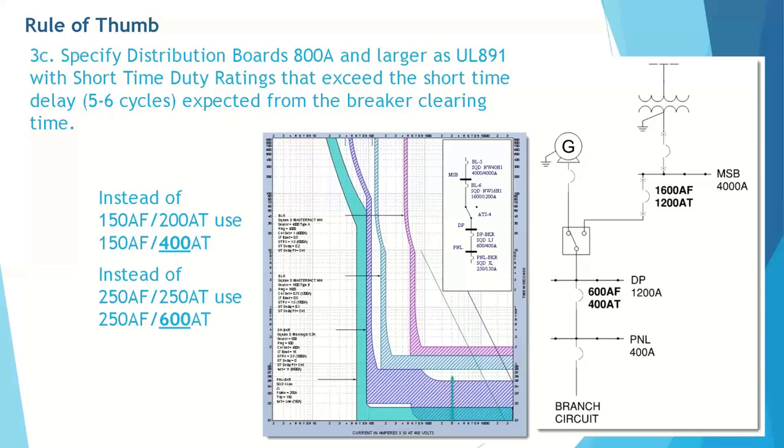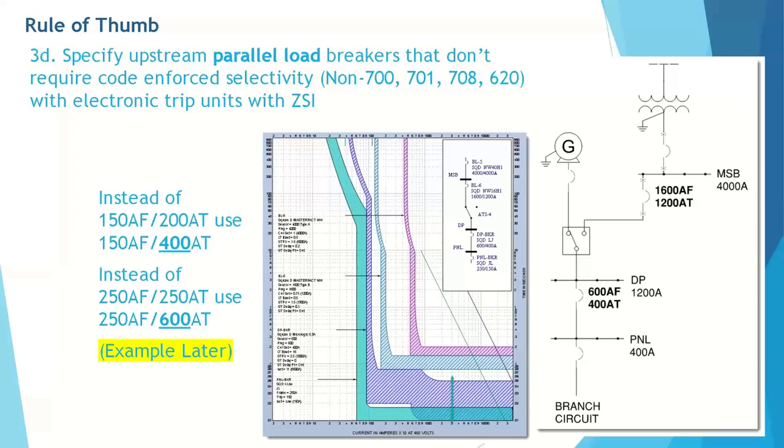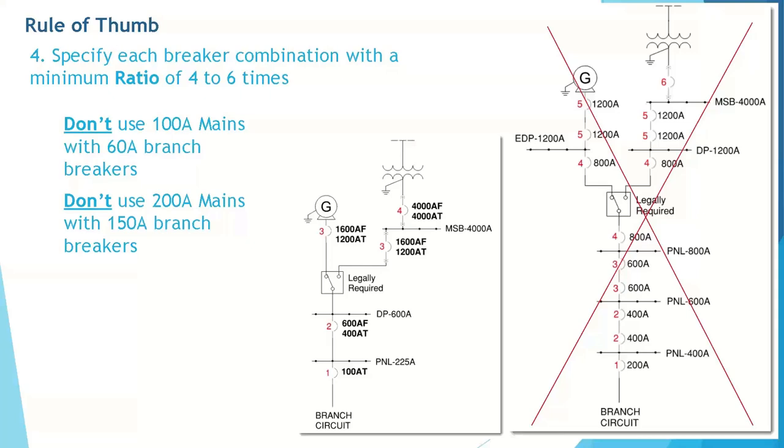For example, instead of using a 200 amp frame and 150 amp trip, you may need to specify a 400 amp frame with that 150 amp trip, or instead of a 250 amp frame, you may need to go up to a 600 amp frame so that you can get a higher instantaneous. For 3B, this is to specify breakers that have a high instantaneous or are capable of having the instantaneous turned off completely. You can see here that this specific breaker can have the instantaneous turned off. For 3C, instead of a typical lighting class panel board, you may need to go up to UL 891 boards to get a higher short time duty rating, ensuring that they exceed the short time delay that you're expected for clearing times.